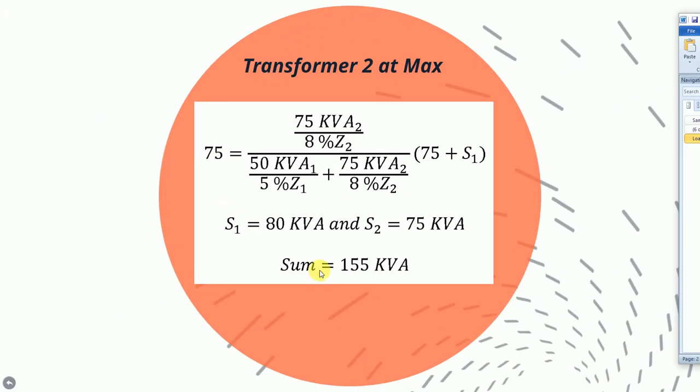Next, let's assume that Transformer 2 is maxed out at its rated capacity of 75 kVA. We plug in the rated capacities and percent impedances for both transformers to solve for S1, the power flow through Transformer 1. This results in 80 kVA through Transformer 1 and the assumed 75 kVA through Transformer 2. This solution is not possible since the power flow through Transformer 1 exceeds its rated capacity of 50 kVA.